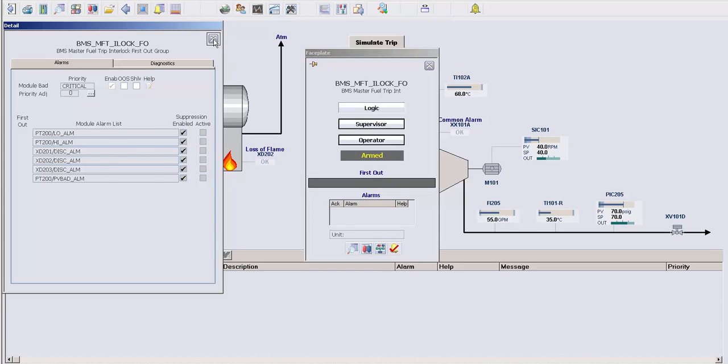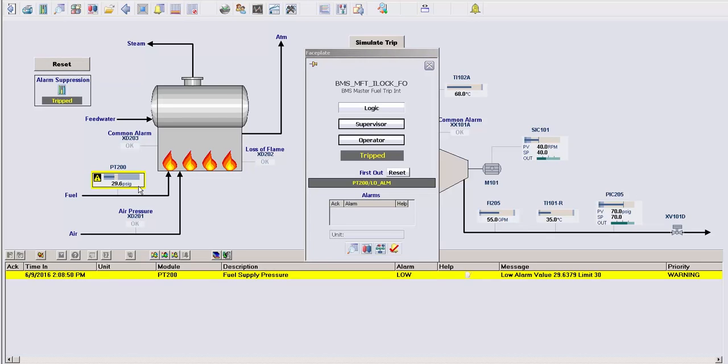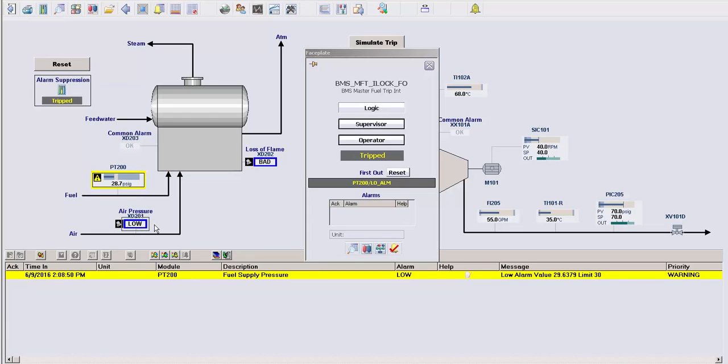But now that the module is armed, let's again trip this boiler to see what happens. As the fuel pressure drops below the low alarm and eventually trips the boiler, you can see that the other alarms are dynamically suppressed and will not show up in your alarm banner.